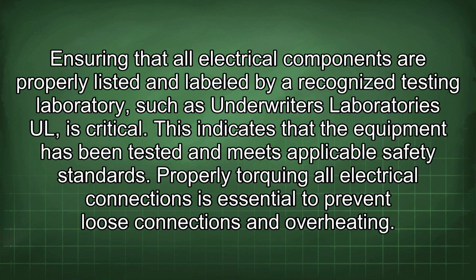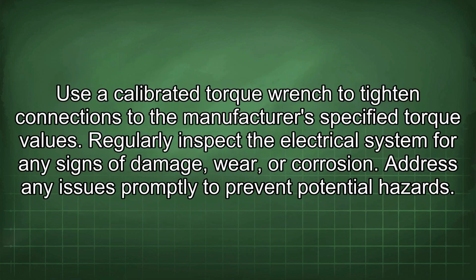Ensuring that all electrical components are properly listed and labeled by a recognized testing laboratory, such as Underwriters Laboratories UL, is critical. This indicates that the equipment has been tested and meets applicable safety standards. Properly torquing all electrical connections is essential to prevent loose connections and overheating. Use a calibrated torque wrench to tighten connections to the manufacturer's specified torque values.